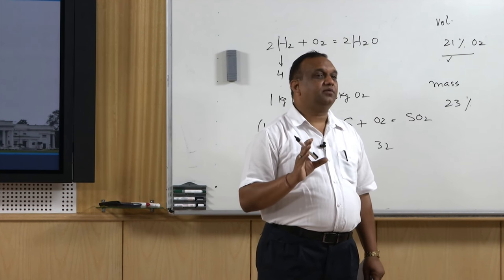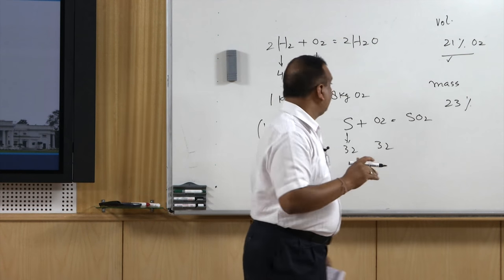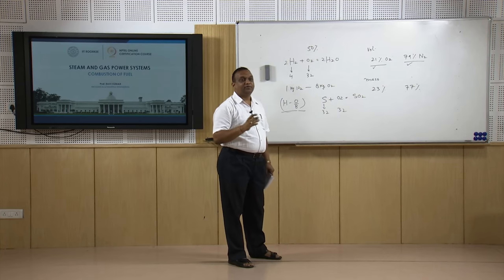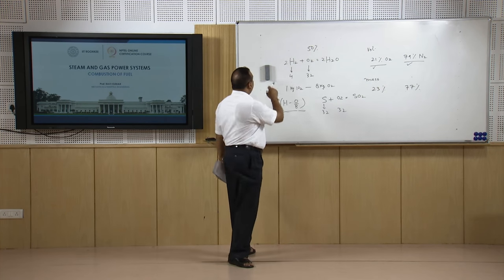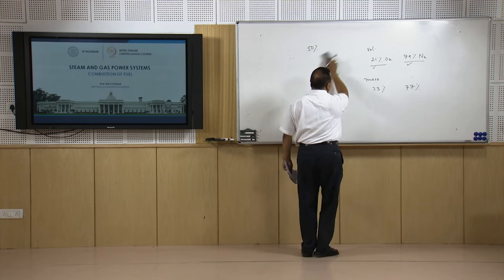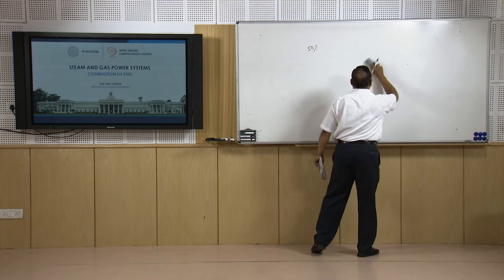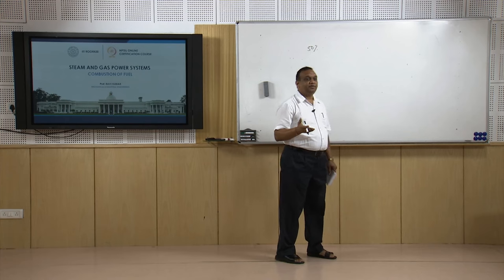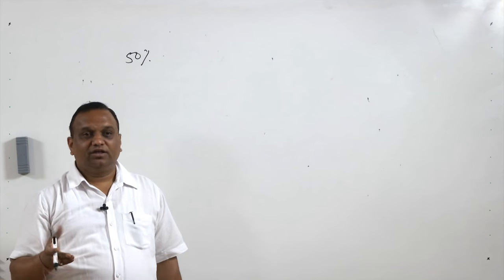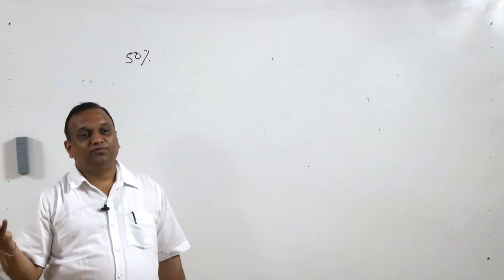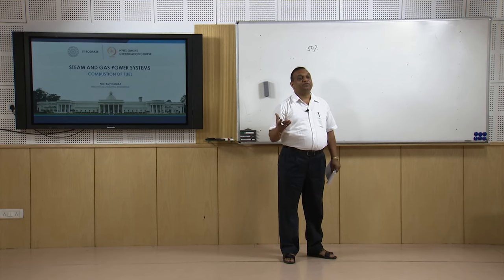Excess air is supplied in the boiler because air is blown over the fuel in a heterogeneous mixture — not a homogeneous one. Excess air can go up to 50 percent. Nitrogen does not participate in combustion, so if you can measure nitrogen in the outgoing flue gases, you can calculate how much air has been used for combustion.